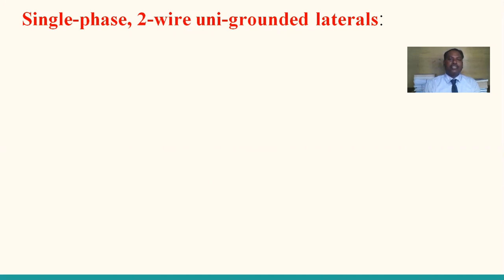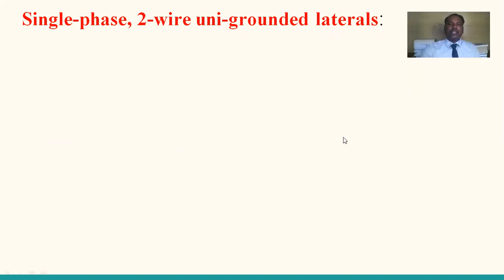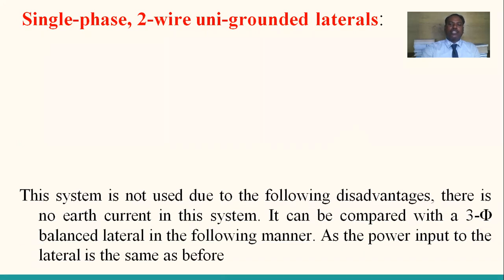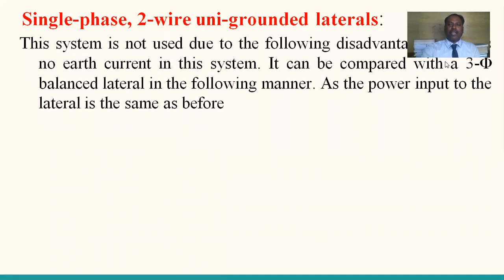So now let us see today's class. We are going to discuss the single phase two-wire uni-grounded lateral. Uni-grounded lateral means single phase two-wire. It has a phase conductor as well as a neutral conductor, but one conductor is grounded. Obviously the neutral conductor may be grounded. This kind of system is compared with the three-phase balanced system to estimate the power losses as well as the voltage drop calculations.